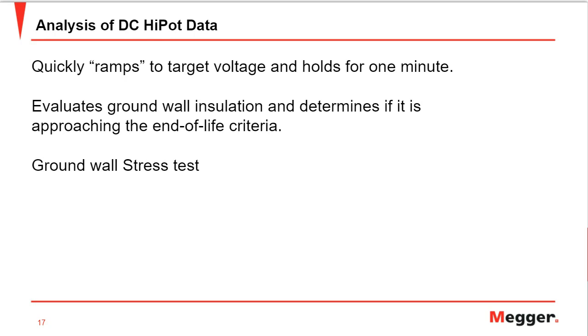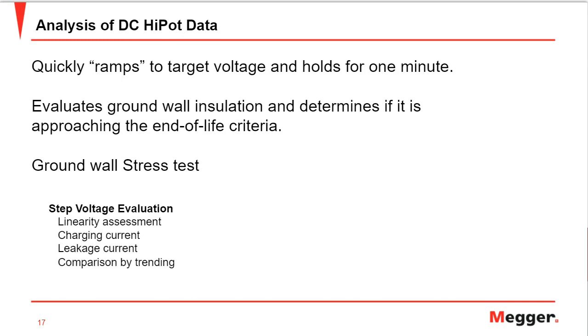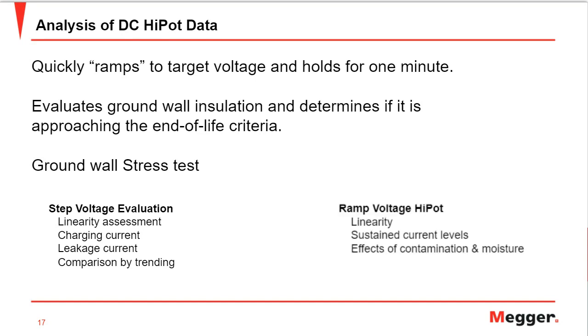There are two types of DC high-pot testing which we can do on a motor. The first is the step voltage evaluation. As the name suggests, the test voltage is raised stepwise, and then the leakage current is measured to see the insulation condition of that particular motor. Another one is the conventional high-pot test, which we discussed, where it ramps to a target voltage and holds for a minute. In both tests, we are just trying to see the linearity of the measured leakage current. Then we determine the health of the insulation according to how linear the chart is once we get the test results.